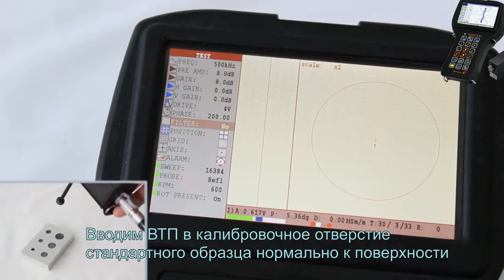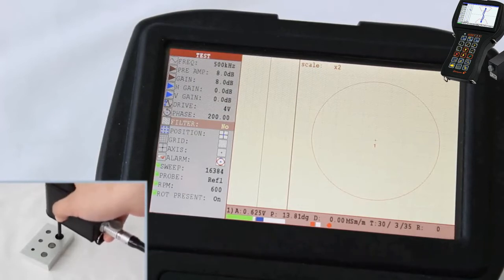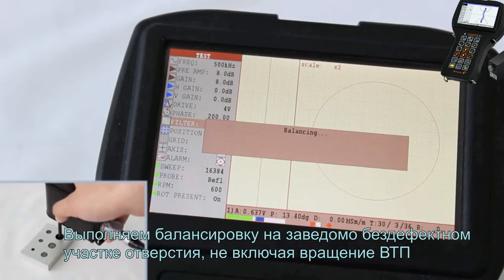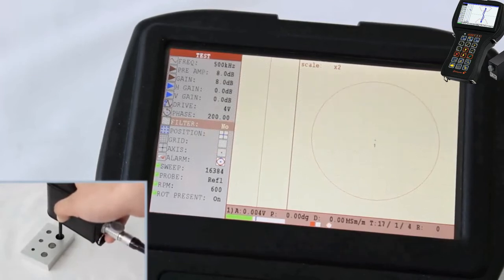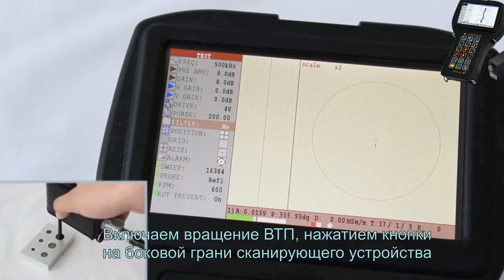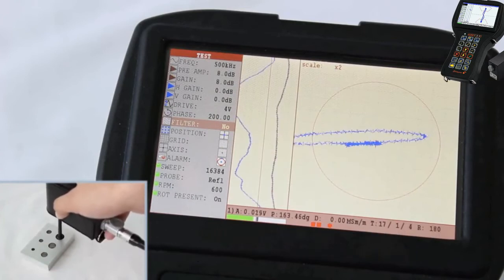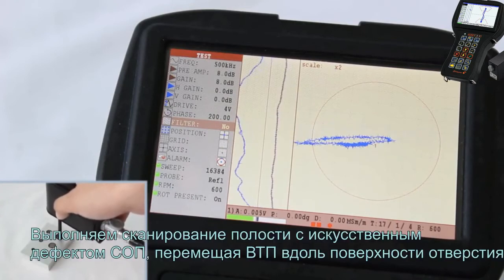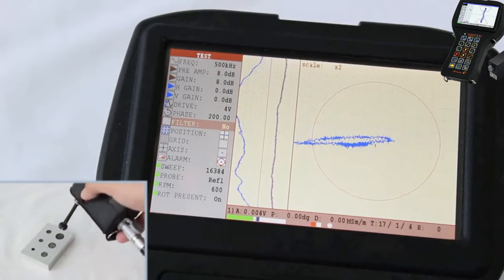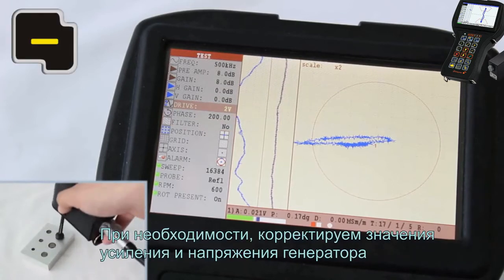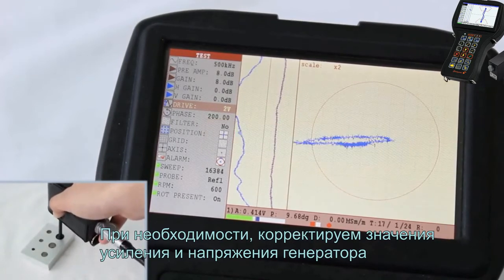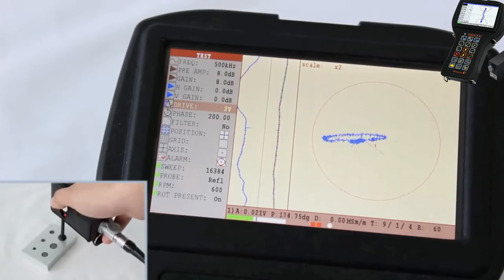Input the EC probe into the calibration hole of a block perpendicular to the surface. Perform the balancing at known flaw-free area of a hole without starting the probe rotation. Start the EC probe rotation by pressing the button on the side face of a scanner. Perform the scanning of a hole with an artificial defect of a calibration block by moving the EC probe along the opening surface. If required, correct the values of a generator gain and voltage.